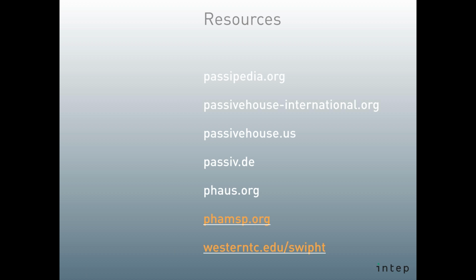So it's a 300 cubic meters an hour unit, nominal capacity, which is 200 CFM. The design airflow for the building is lower than that. I would say it's probably around 100, 120, something like that. I'm doing this from memory, don't hold me to it. And so the machine is going to run in a partial load scenario in everyday use, which is actually beneficial because it ups the efficiency of the heat exchanger.